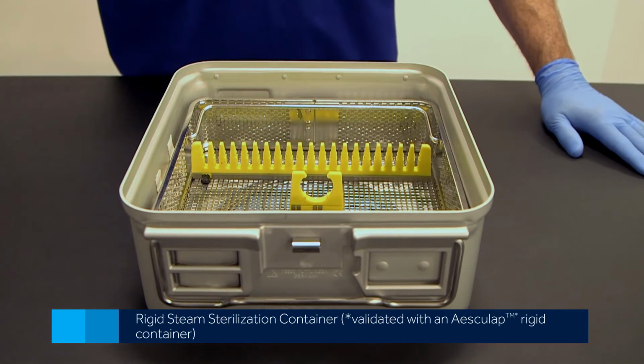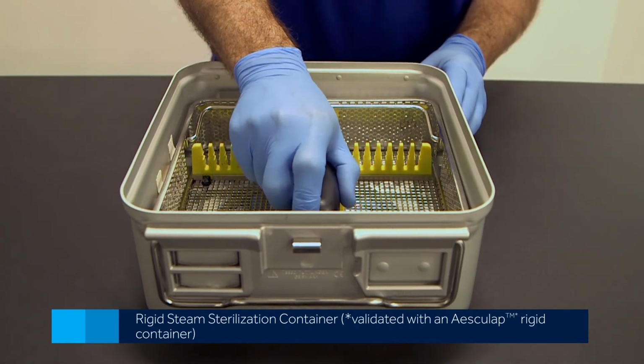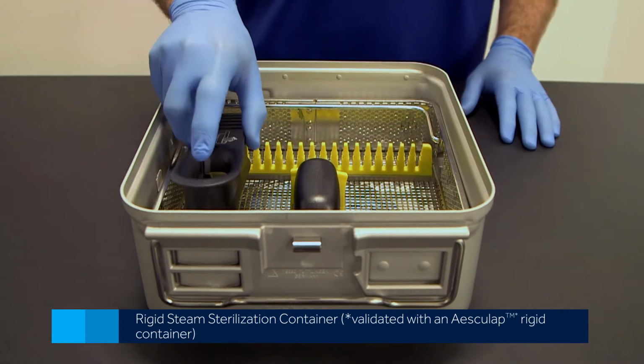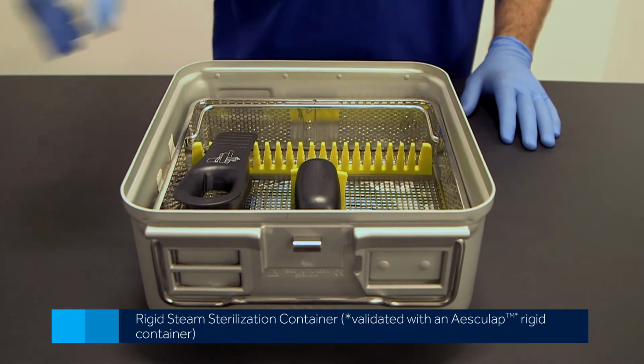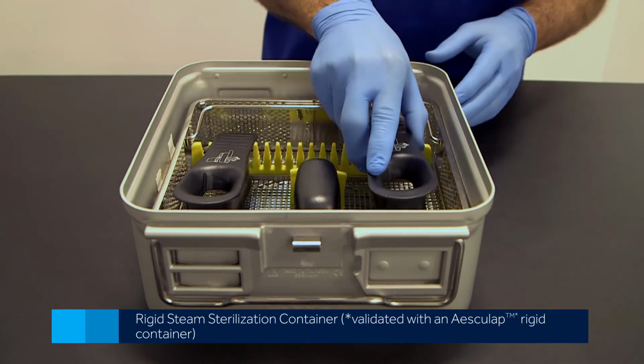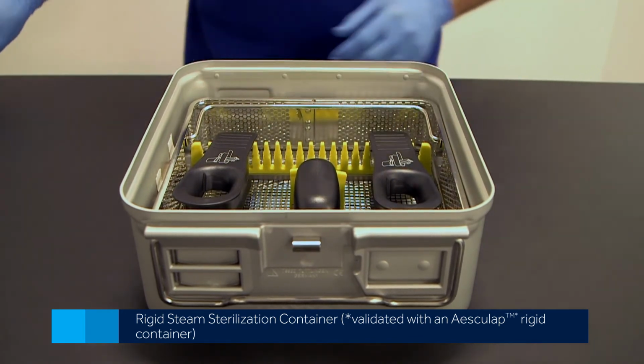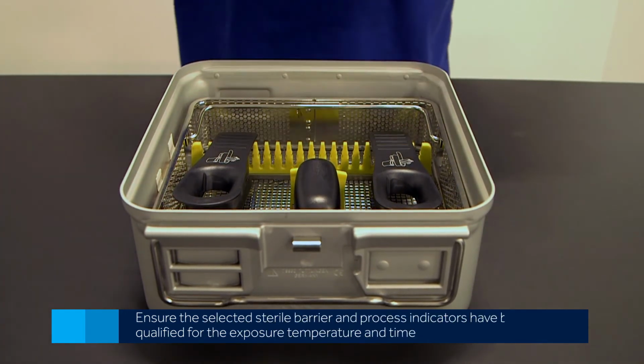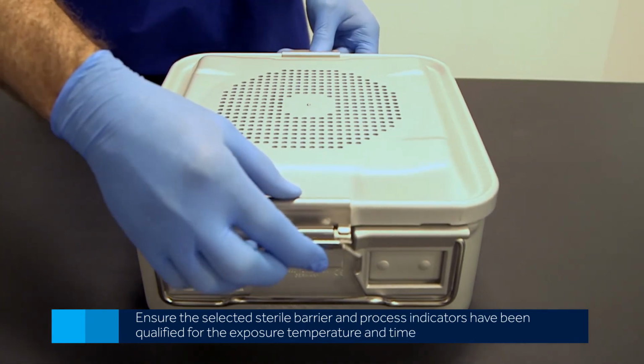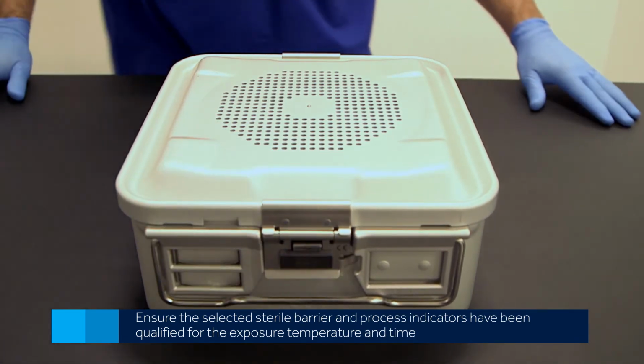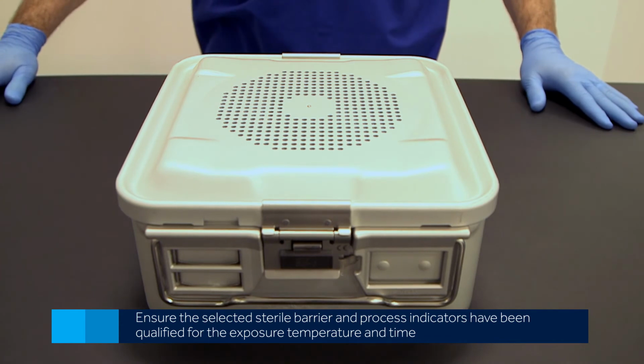When using a rigid steam sterilization container, place the components in a compatible rigid steam sterilization container. Ensure that the individual components are not touching and the container is loaded according to manufacturer's recommendations. Ensure that the selected sterile barrier and process indicators have been qualified for the sterilization exposure temperature and time that will be used. Warning: do not use alternative sterilization barriers or additional absorbent or protective material, as this may compromise sterility or functionality of the components.